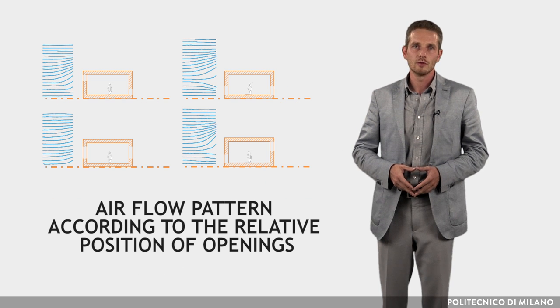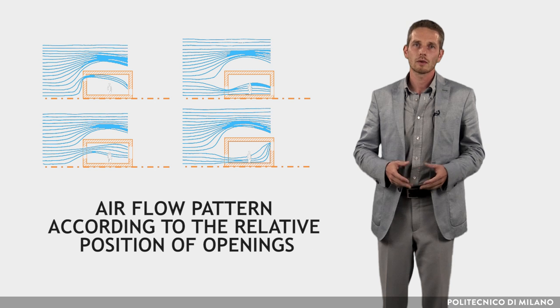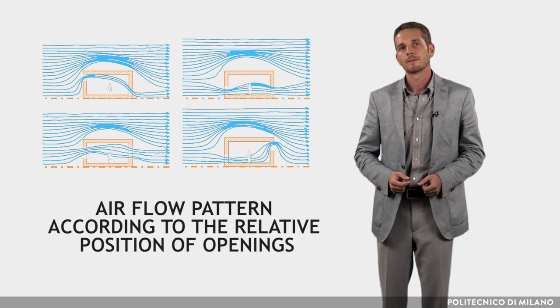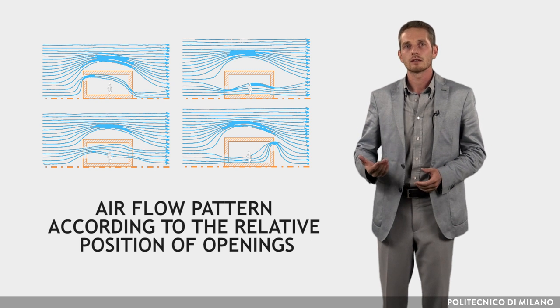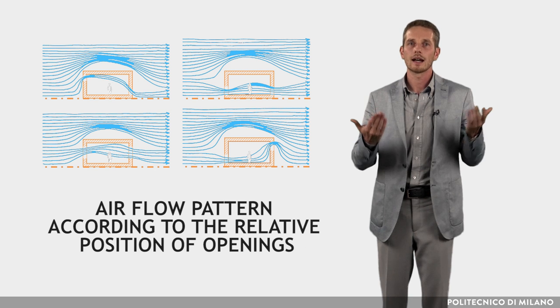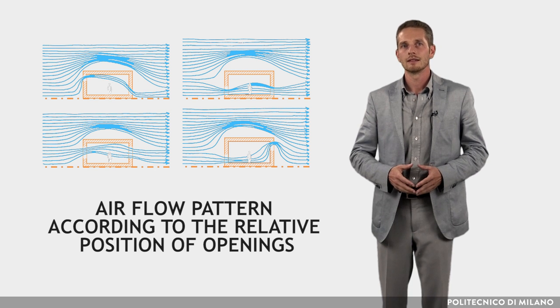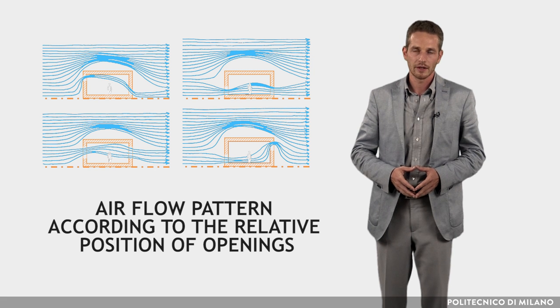The airflow pattern due to the wind depends on the relative position of the openings. The best conditions are created when outlet openings are higher and wider than the inlet. The ideal is to have them of equal area.